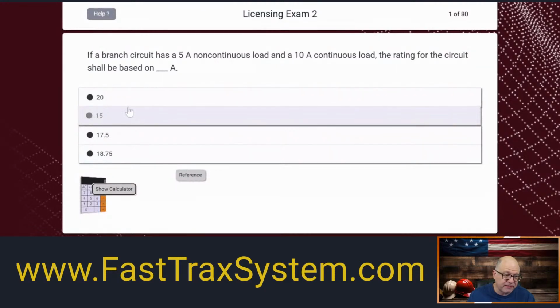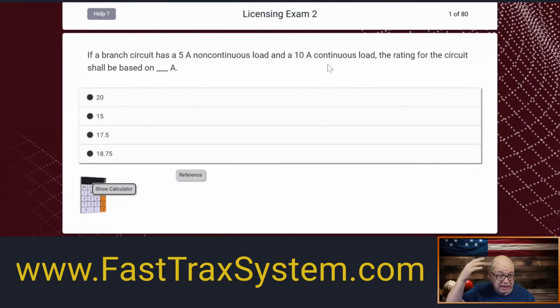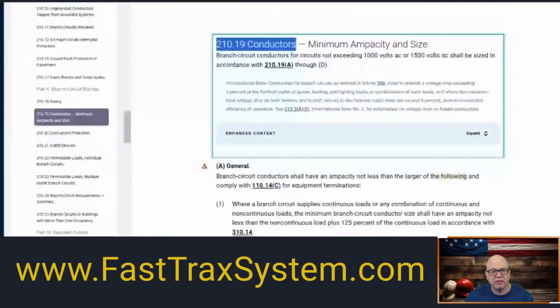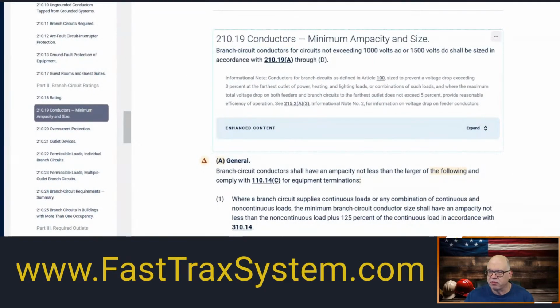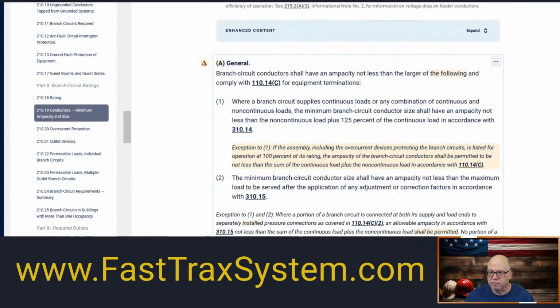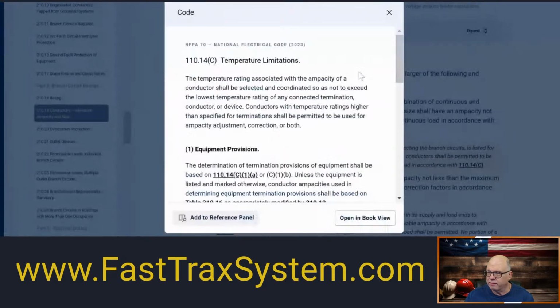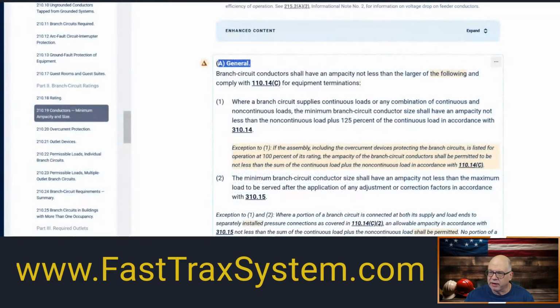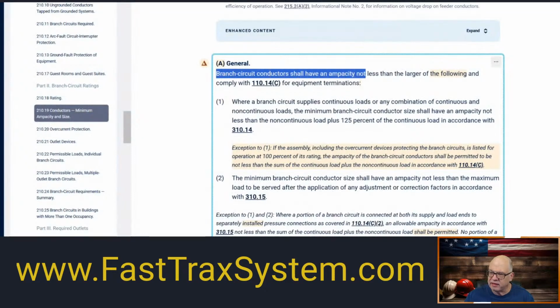Now it would be 15 if this was 5 amps of non-continuous load and another 10 amps of non-continuous load. Then you'd just be adding the two together, right? Because they're both non-continuous loads. That's not what we got here. So let's go to this tab. So we're at 210.19 general right here. It says, oops, let me get rid of that.